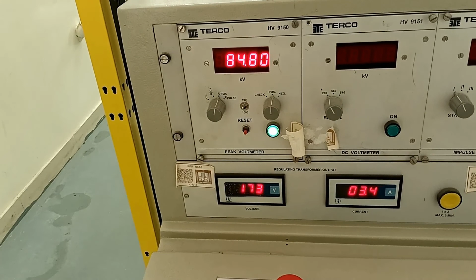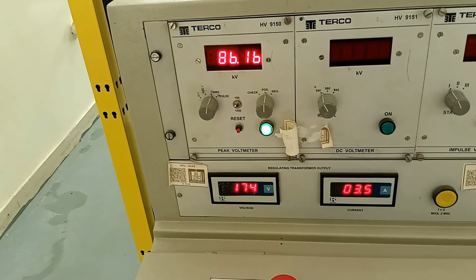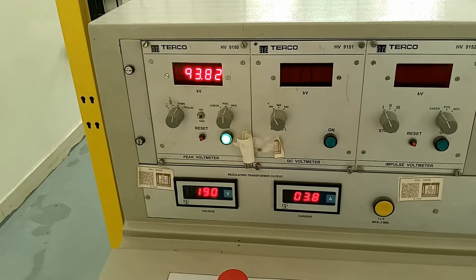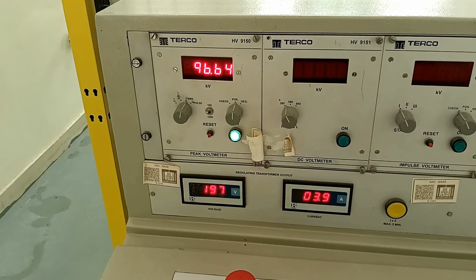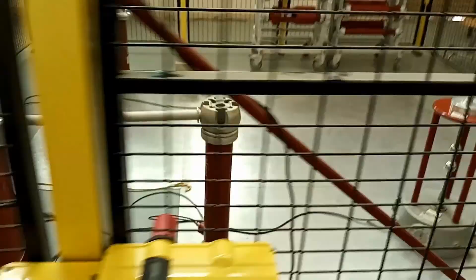You will find a difference now - you can hear some noise, some humming noise is there. For 175 you got around 86. When we reach the higher voltage, setting it to 200 - 190, and now changing it to 200 - see, almost 100 kilovolts. You can hear some humming noise near the capacitor. This humming noise is because of the ionization around the terminals, around the capacitors. That's it.